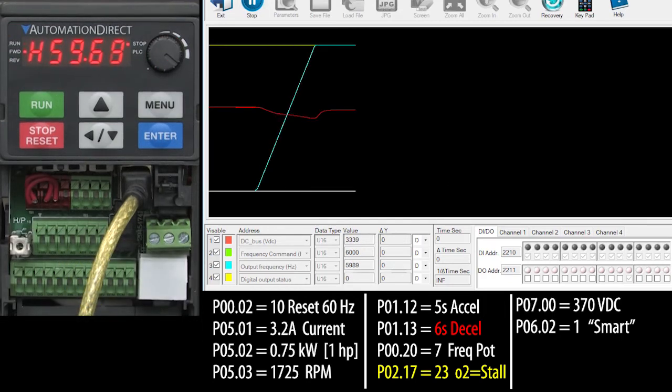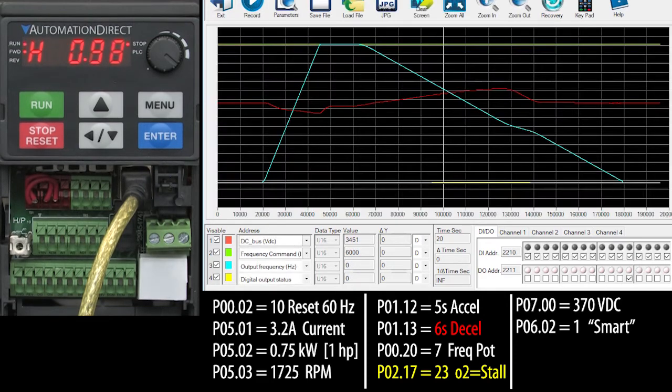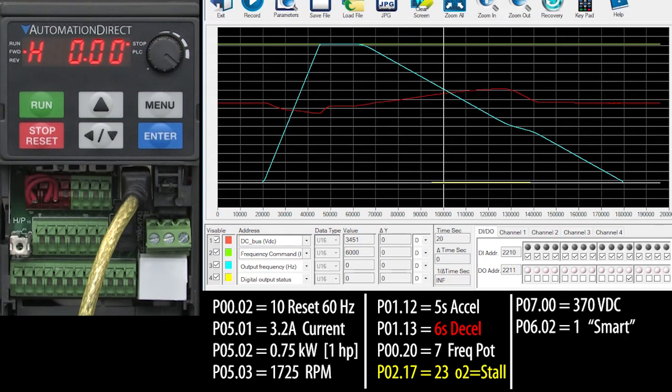I did some experiments and I had to change the deceleration time all the way out to 21 seconds before the fault went away. That looked like this.